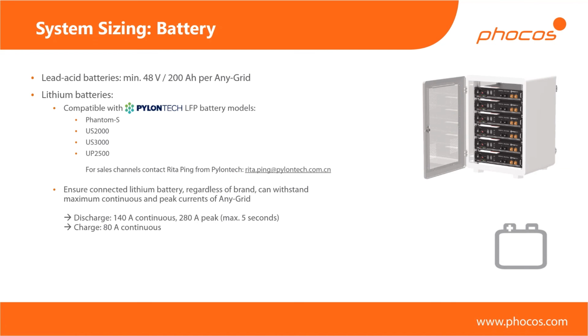project. If you're using lithium batteries that are not from PylonTech, then for the moment, we don't have any others implemented in terms of communication. So you would need to make sure that they have a battery management system that does not require communication with the inverter.